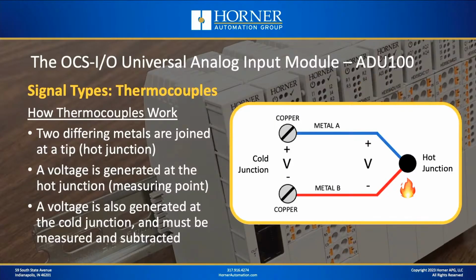How do thermocouples work? Thermocouples take advantage of the material properties of metals. If you take two different metals and join them at the tip, a voltage will be generated at the point where they're joined that varies with temperature. That tip, called a hot junction, can be used as the measuring point for your temperature, and it will generate a different voltage as the temperature changes. One thing to consider, though, is that the voltage generated is very small. It's only in the millivolts range, a few millivolts or so. Because that is such a small signal, relatively speaking, that's one of the reasons why thermocouples can be susceptible to electrical noise.